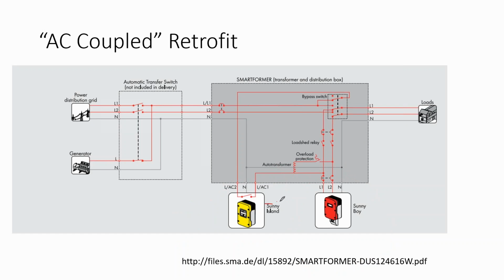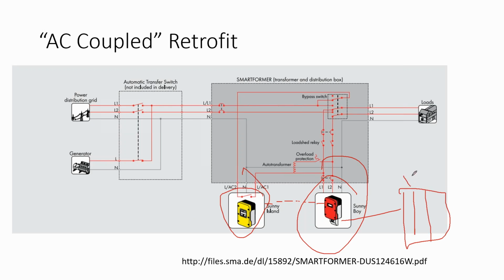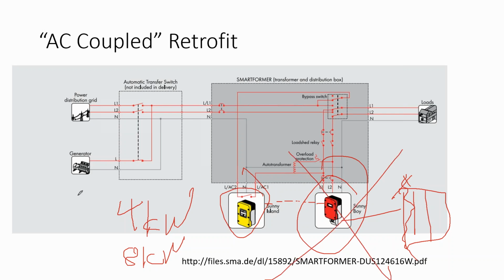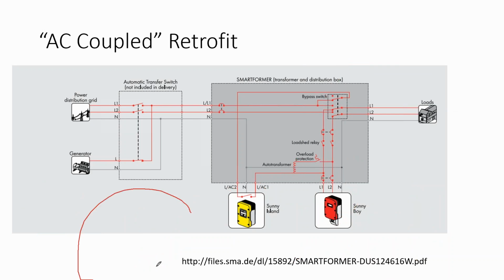Now, what's interesting, if you use an elegant solution, like the SMA battery inverter and the SMA solar inverter, it'll actually just dial back the solar array and maybe only turn one circuit off. Say, hey, our load is at 4 kilowatts and our solar array is at 8 kilowatts. And so in one circumstance, you would be turning off the inverter and then drawing down the batteries and then turning the inverter back on and then filling up the batteries. And that's using your batteries. That's cycling your batteries. That's taking life out of the batteries.